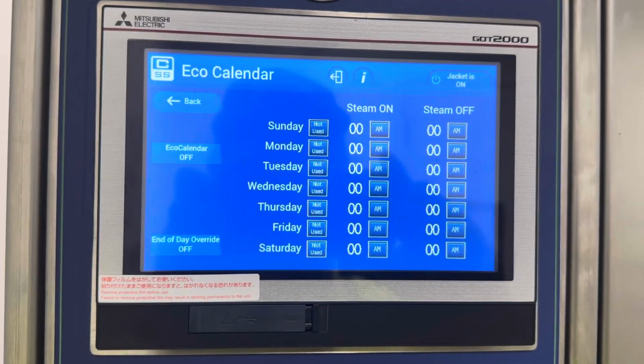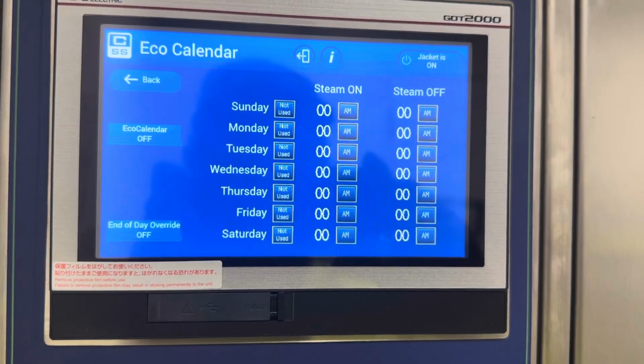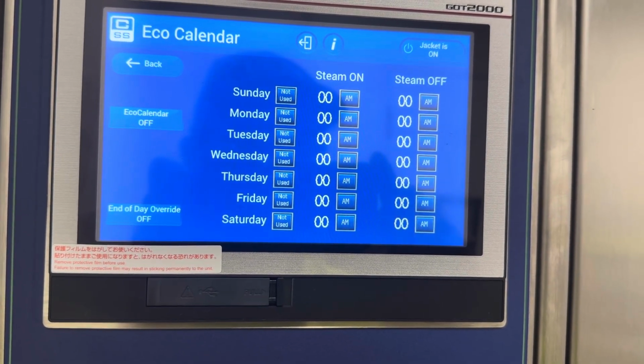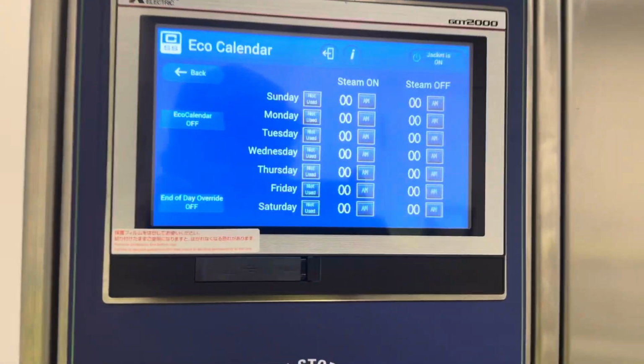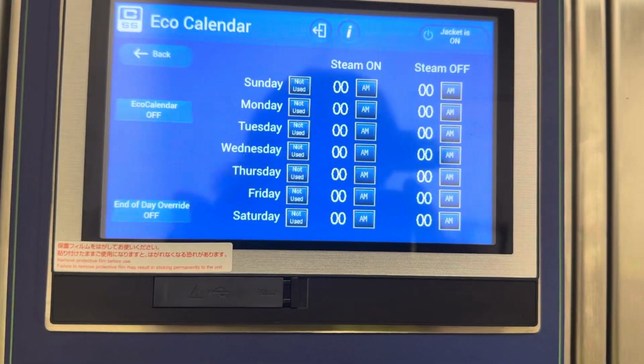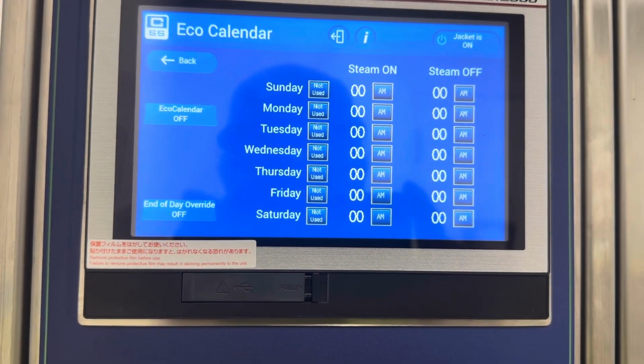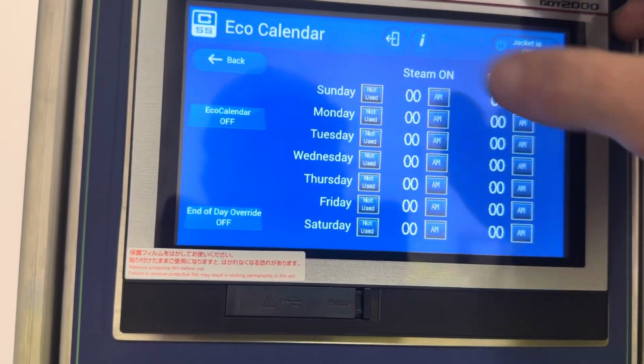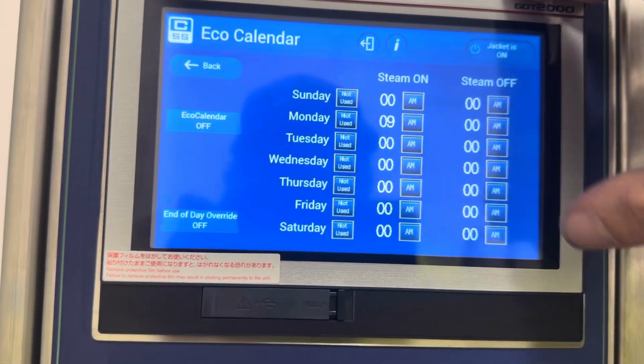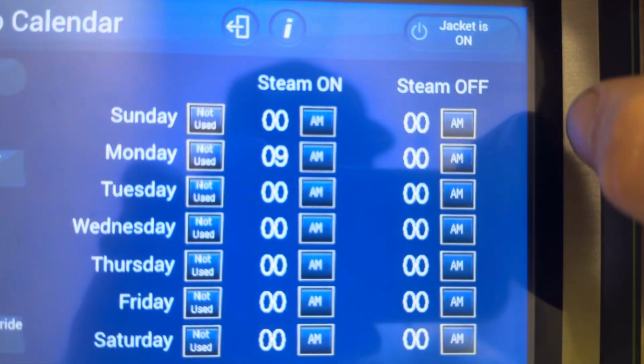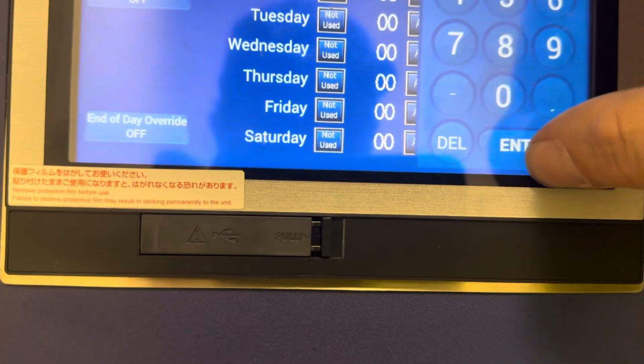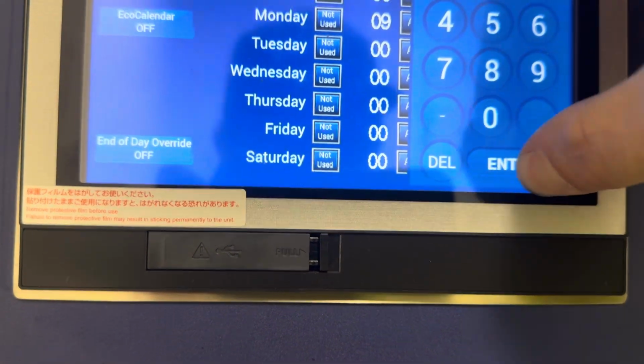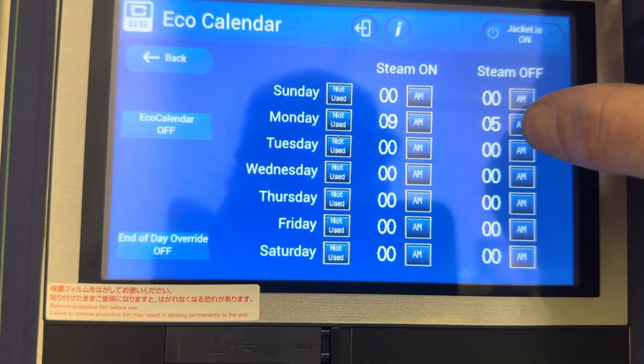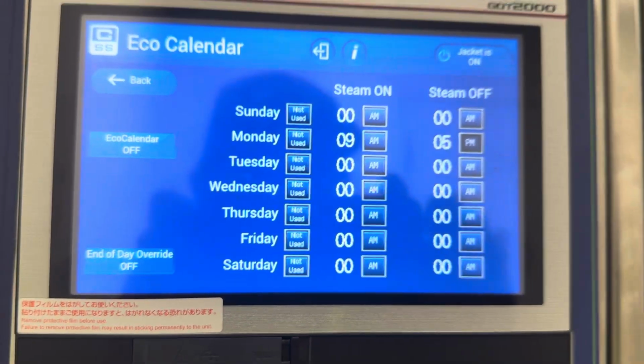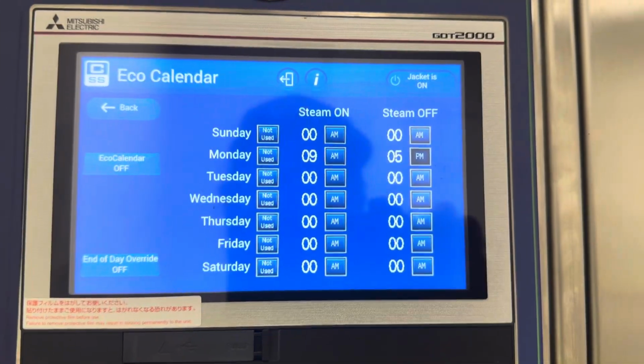Back to the Eco Calendar. If you get on a consistent schedule where you want this autoclave to be on at a certain time, say I normally come in at 8 and I start preparing my loads at 8:30 after I check my emails, I can program this machine to come on at 9 a.m. and go off at 5 p.m. Make sure to switch AM to PM for whichever time you choose for it to come on.